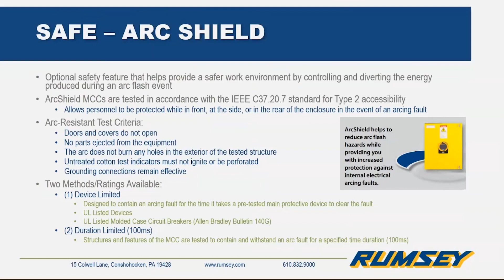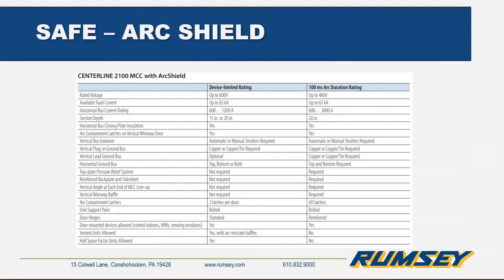So here's just a visual comparison between device limited and duration limited ratings. You can think of the duration rated version as being like a beefed up version with reinforced door hinges, back plates, and additional grounding. It also has additional features that device limited MCCs do not have, such as a pressure relief system at the top and wireway baffles on some of the unit doors. It is important to note that although you might get a little bit more protection with the duration limited, you are not able to put in half space factor units or vented units in the MCC.